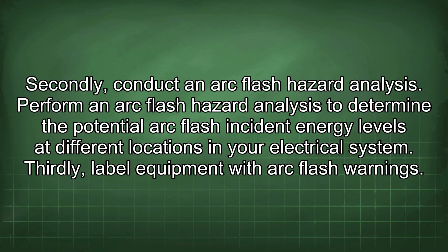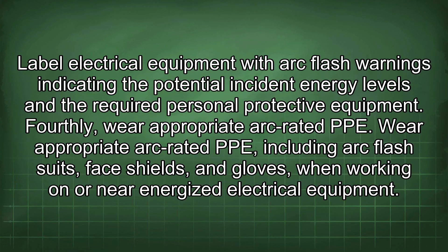Thirdly, label equipment with arc flash warnings. Label electrical equipment with arc flash warnings indicating the potential incident energy levels and the required personal protective equipment. Fourthly, wear appropriate arc-rated PPE. Wear appropriate arc-rated PPE, including arc flash suits, face shields, and gloves when working on or near energized electrical equipment. Fifthly, reduce arc flash hazards. Implement measures to reduce arc flash hazards, such as using remote racking devices, current limiting fuses, and arc flash relays.